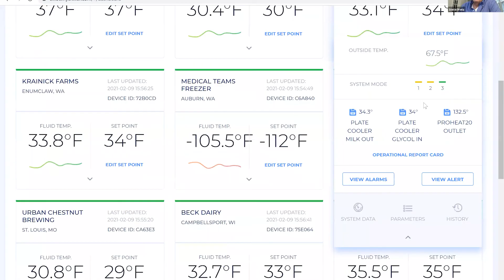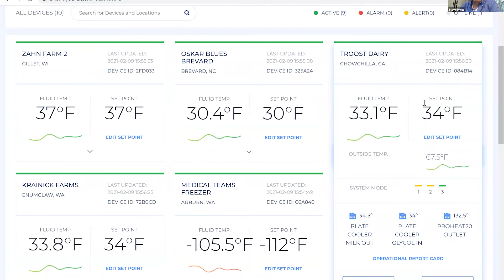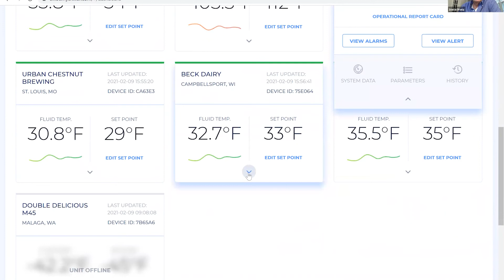These are probably the biggest things a dairy farmer would look at. We'll look at another farm that's always interesting for me because they're using it a little differently. This customer, when we put this system in, this is in a different part of the world, in Wisconsin. He had some limitations on well water, and he's keeping track of the cooling that's done only with well water. With our plate design, we're able to segregate those two pieces, the glycol side and the well water side.